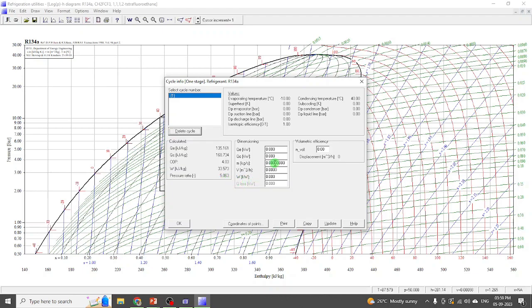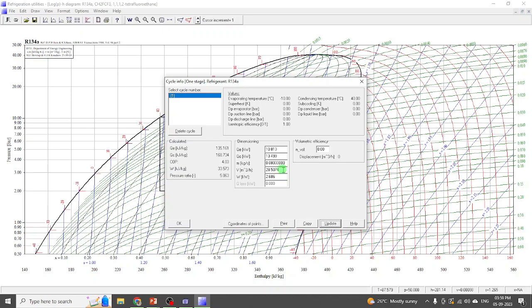You can see the COP value from CoolPack software is also matching our analytical calculation. In our analytical calculation we got COP as 4.03, and by using CoolPack software we are also getting the same value of 4.03. The work input is 33.573 kJ/kg and the pressure ratio is 5.063.